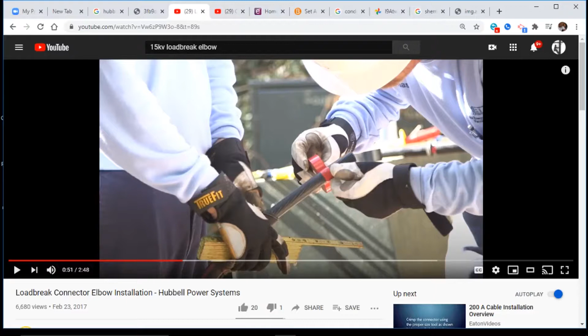Measure 2 inches down from the end of the cable. Okay, so I'm going to stop right here. He's going to start getting into rulers and measurements. Both Hubbell and Elastimold, that's another manufacturer of 15 kV or any other kV load break type elbows, every single box or package that they come in now has a template. So all you'll have to do is put that template up beside the conductor right here and make measurements. You're not going to need a ruler, and that template in every single package is precise, so you know you can use it.